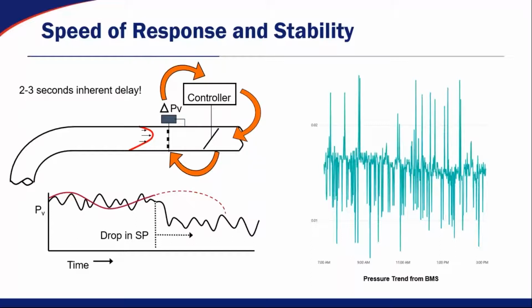So if the building goes occupied at 8 o'clock in the morning, they start the transition at 7:30. So the fans and all the VAV boxes have a chance to settle out before the occupants come in, and they get their comfort control up to where it should be. So it does cause some problems inside of a building just to slow down the control loop to get more stable control.